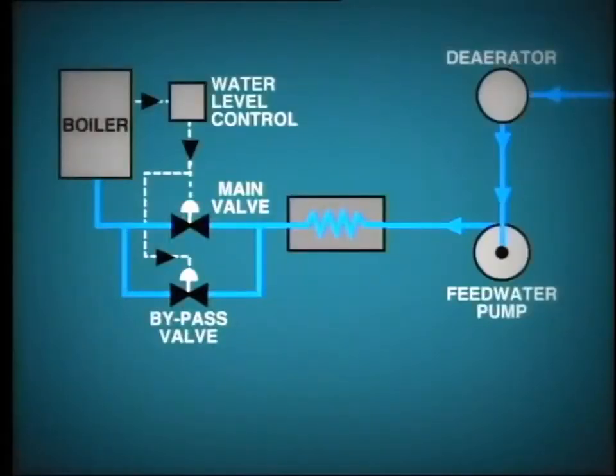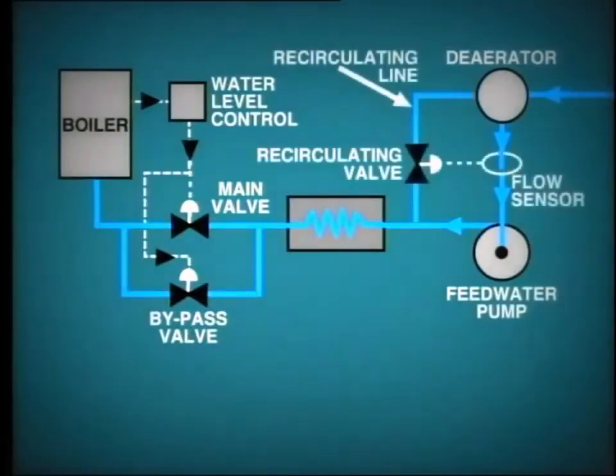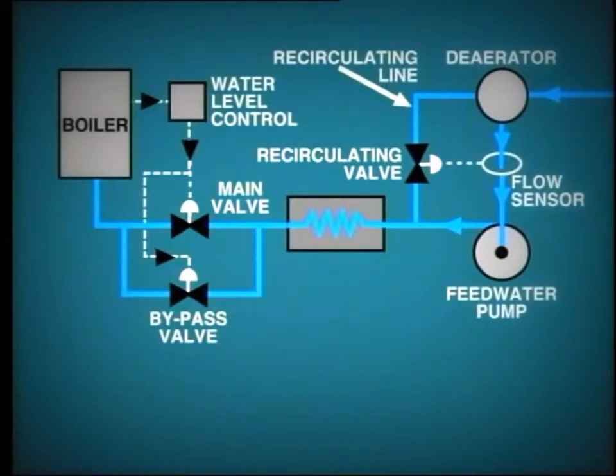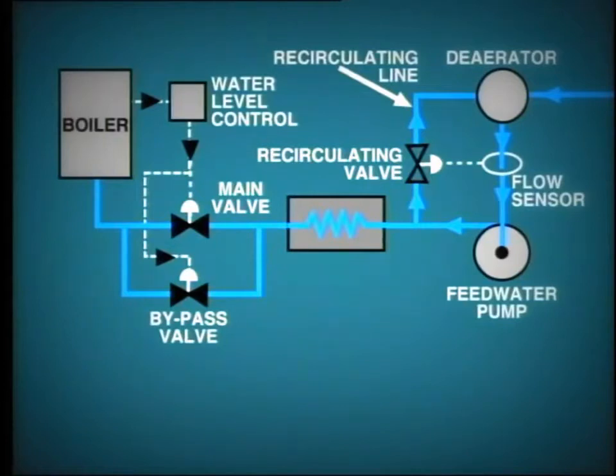In order to prevent this problem, a recirculating line is fitted to the pump discharge. In the event that the feedwater flow through the pump falls below a preset minimum, the recirculating valve opens automatically and passes water directly back to the deaerator, thus maintaining the pump in a safe operating condition.